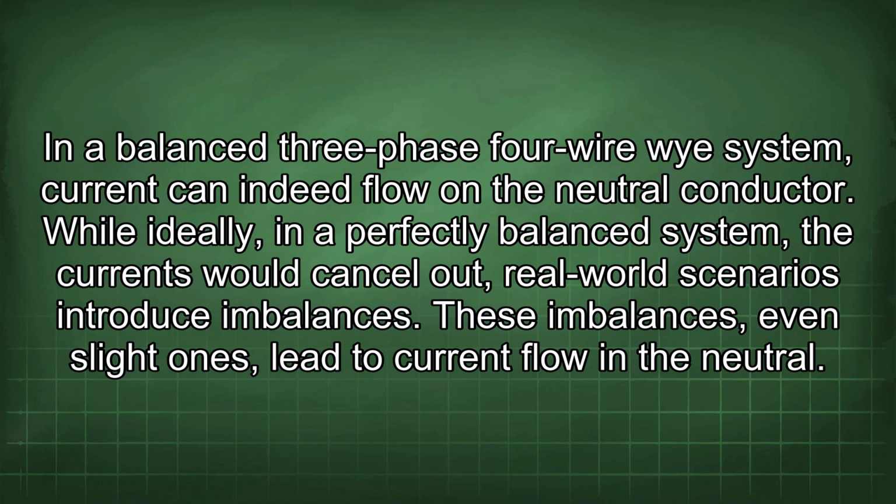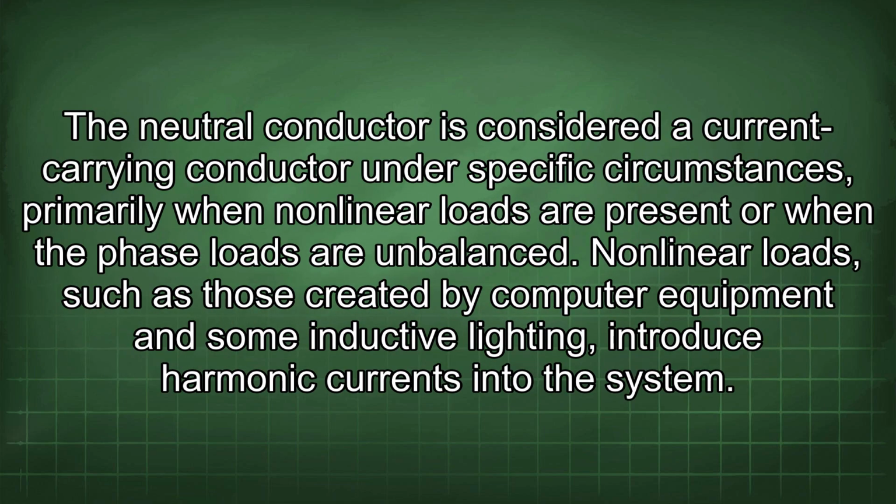In a balanced three-phase four-wire Y system, current can indeed flow on the neutral conductor. While ideally, in a perfectly balanced system, the currents would cancel out, real-world scenarios introduce imbalances. These imbalances, even slight ones, lead to current flow in the neutral.